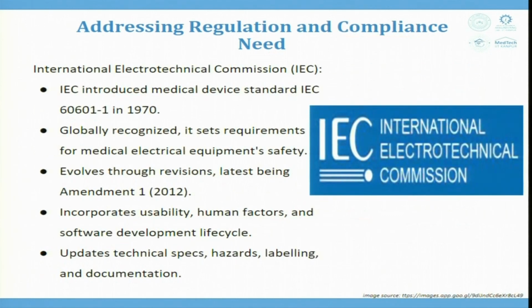Now, when we are talking about the regulation, the IEC, that is International Electrotechnical Commission, introduced medical device standard IEC 60601 in 1970. It is globally recognized and it sets requirements for medical electrical equipment safety. It evolves through revisions, latest being Amendment 1 2012, which covers the electrical noise that is coming out of the device. For example, even if you are using the mobile phone, or if I am using the Wi-Fi router in this room, they are also emitting some electrical signals. These signals should not harm the human body. These are the general compliances.